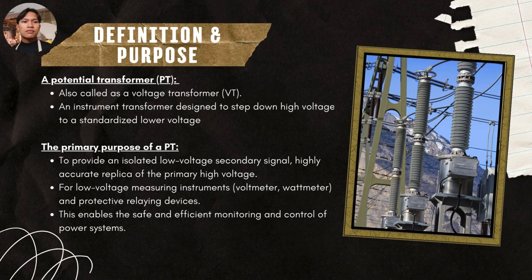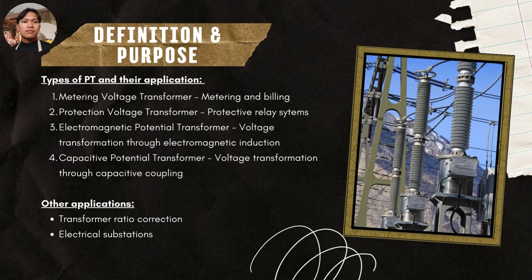Now moving on to the last transformer — the potential transformer, also known as the voltage transformer. It is an instrument transformer designed to step down high voltage to a standardized lower voltage. Its primary purpose is to provide an isolated low voltage secondary signal which is a highly accurate replica of the primary high voltage, for use with low voltage measuring instruments such as voltmeters and wattmeters, and protective relaying devices. Applications include metering and billing, protective relay systems, voltage transformation through electromagnetic induction or capacitive coupling, transformer ratio correction, and electrical substations.